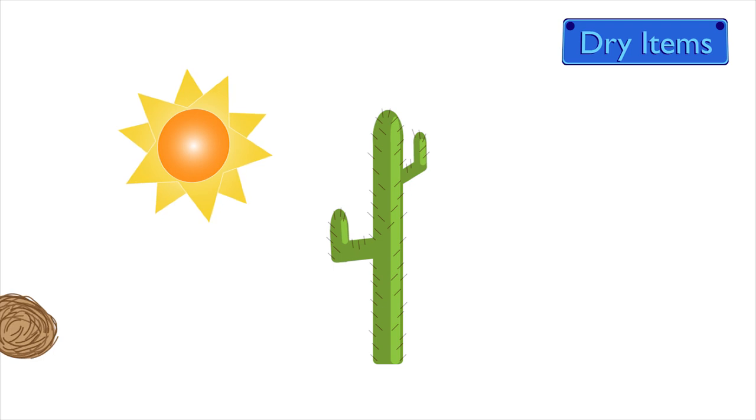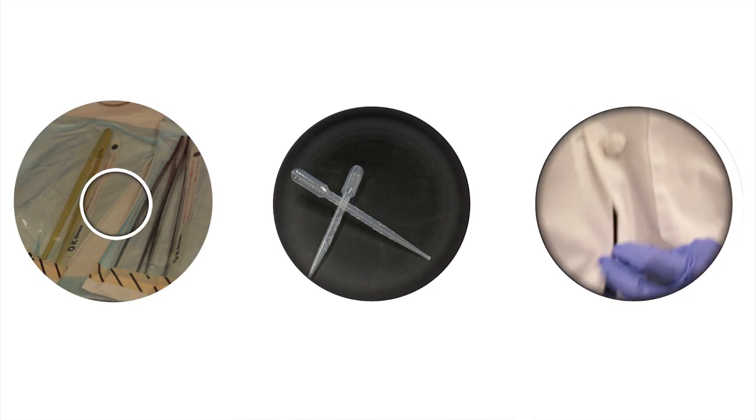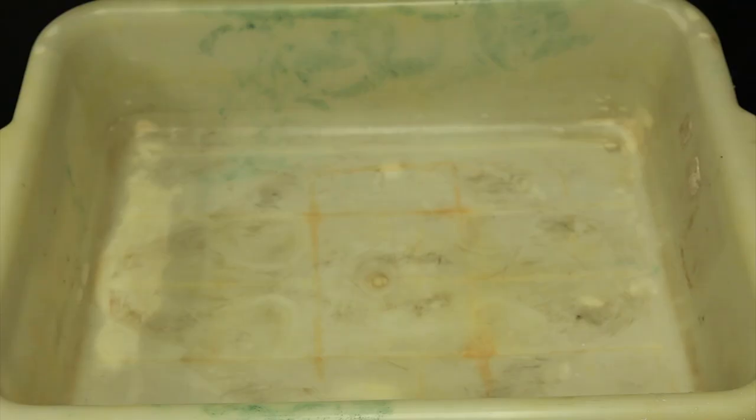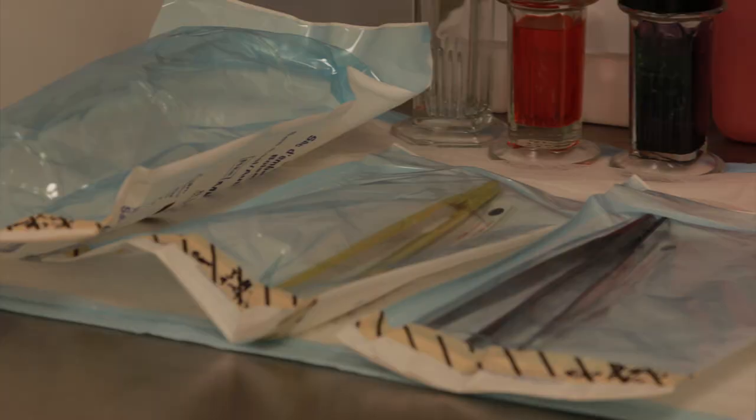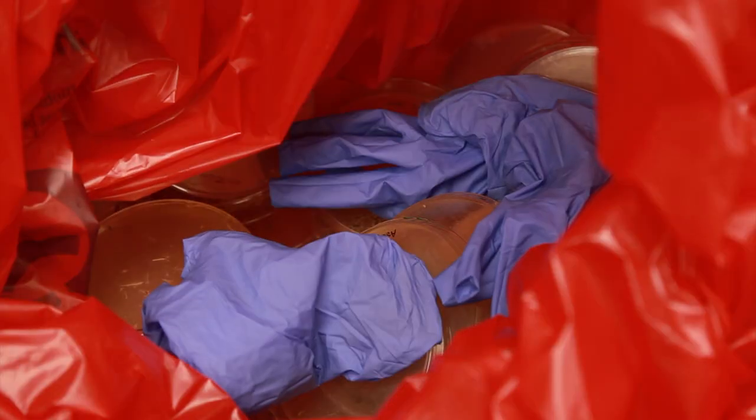Dry items. Dry items include instruments, surgical tools, plastic ware, and fabrics, and must be placed in a metal or autoclave rated plastic pan or tray. Instruments are often packed inside a self-sealing autoclave envelope along with a sterilization indicator. Once closed, autoclave tape is affixed to the outside of the package. The packages are then placed into a rack or loosely arranged in an autoclave-resistant pan. If items in this category are contaminated with biohazardous materials like used pipette tips, petri dishes, or gloves, they must always be in a red biohazard bag and never loose prior to autoclaving.